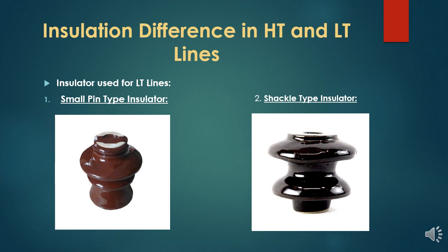High-tension line and low-tension line also differ in the insulators used. Since the low-tension line voltage level is lower, the insulators used are of different categories. In the low-tension line, we use small pin-type insulators or shackle-type insulators. These are common insulators that insulate the transmission line from towers. These pin-type and shackle-type insulators are basically designed for the voltage level of the low-tension line.